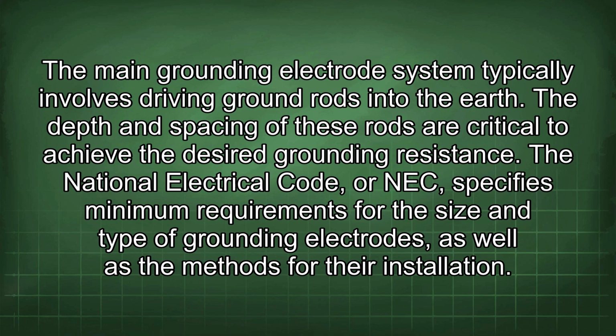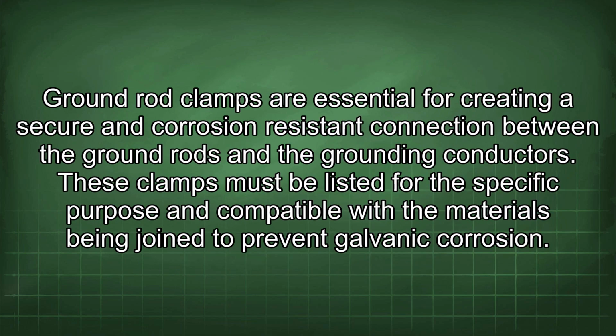The National Electrical Code, or NEC, specifies minimum requirements for the size and type of grounding electrodes, as well as the methods for their installation. Ground rod clamps are essential for creating a secure and corrosion-resistant connection between the ground rods and the grounding conductors. These clamps must be listed for the specific purpose and compatible with the materials being joined to prevent galvanic corrosion.